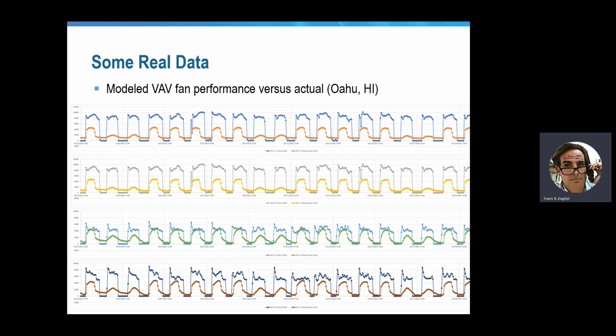The second thing to look at is the actual shape of the curve. This energy model assumed a profile where there's a peak and then there's kind of a rapid drop off in the next 2 hours. And that is pretty much universally wrong for all of these air handlers. Those afternoon airflows after 3 p.m. are staying high. So even if these lines were at the same level, the shape of the curve, the plateau, we would incur more fan power.